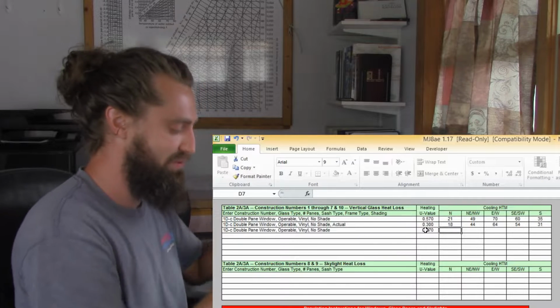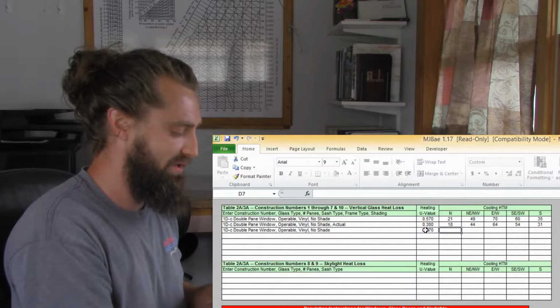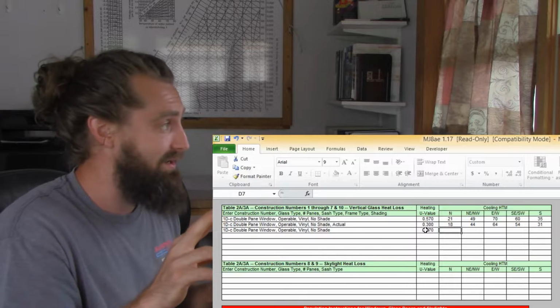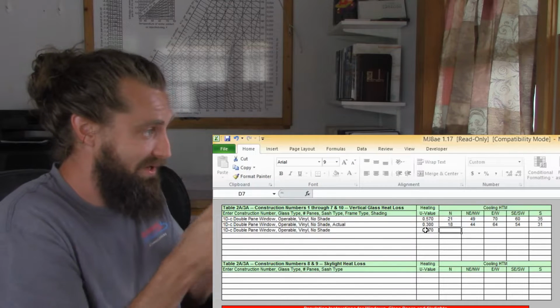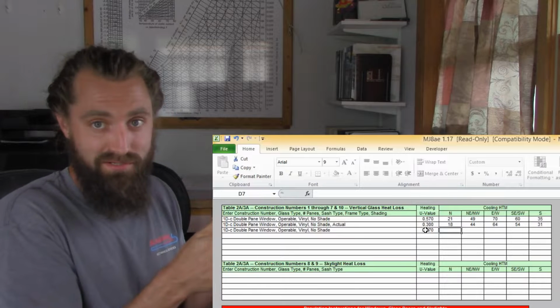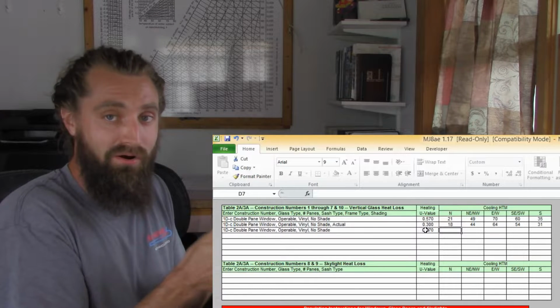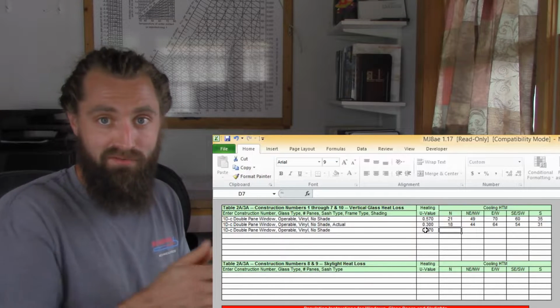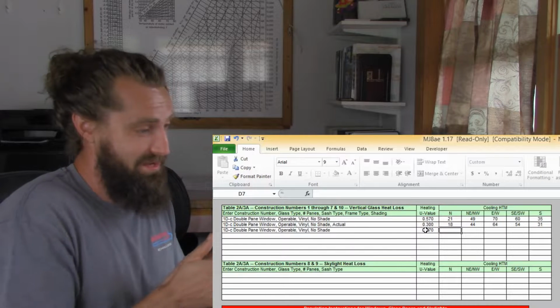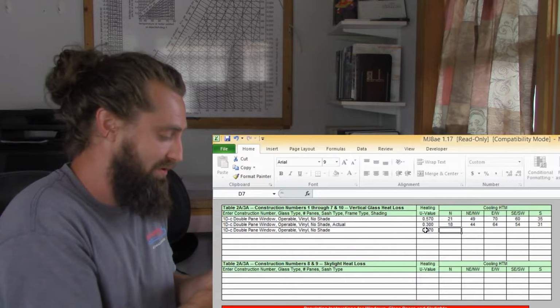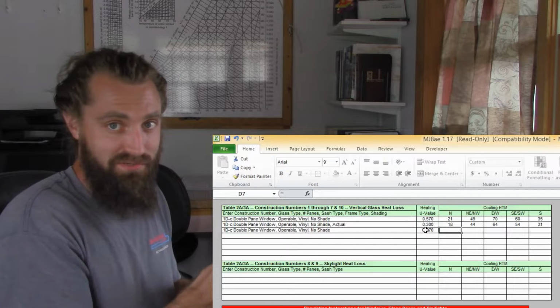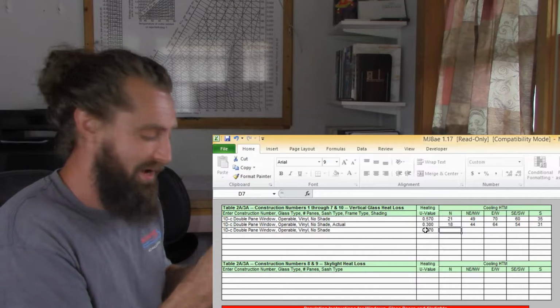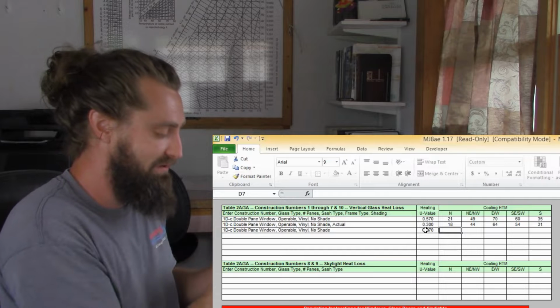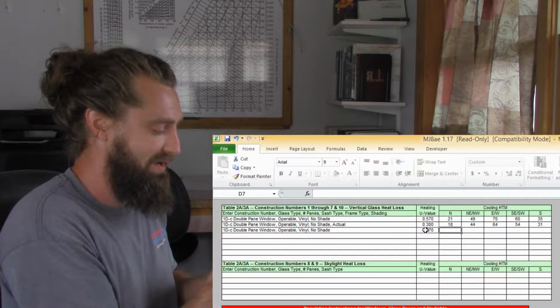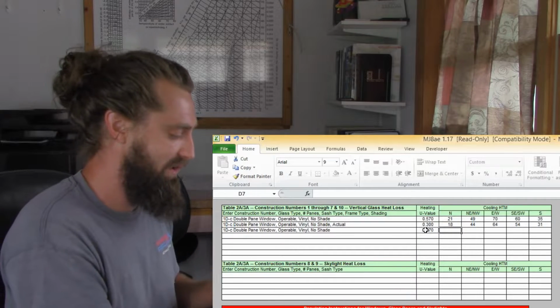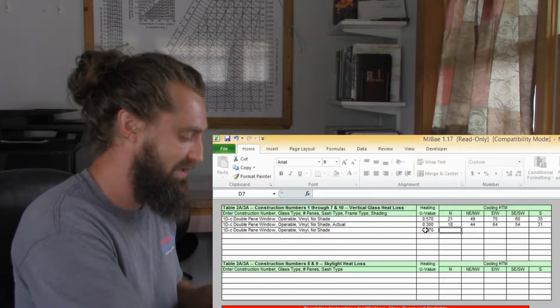0.57. Now we're going to input the 20 degree column. So we're kind of interpolating some numbers here—what our actual heat transfer multiplier for that specific window is going to vary, but we've only been given 2 different numbers to work with. So we're going to choose the low and the high side: the 15 heat transfer multiplier category for the first one, and the 20 for the next one. I'm going to input all of the 20 differential information into this.